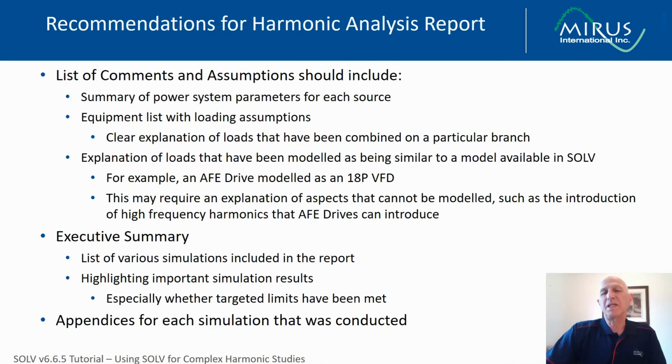Now that we've completed the various simulations, they can be easily assembled into a concise and easy to follow report. Our recommendations on how to organize such a report are to include a list of comments and assumptions with the summary of the power system parameters for each source, the equipment list with loading assumptions, and a clear explanation of loads that have been combined on a particular load branch, explanation of loads that have been modeled as being similar to a model available in SOLV.